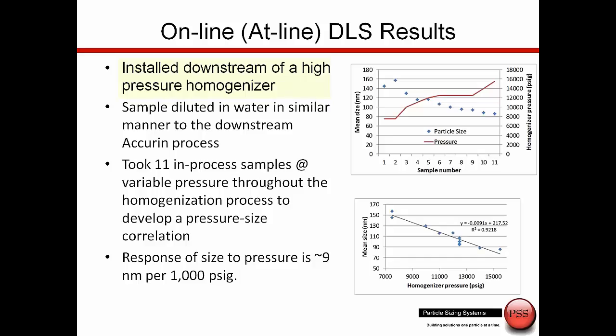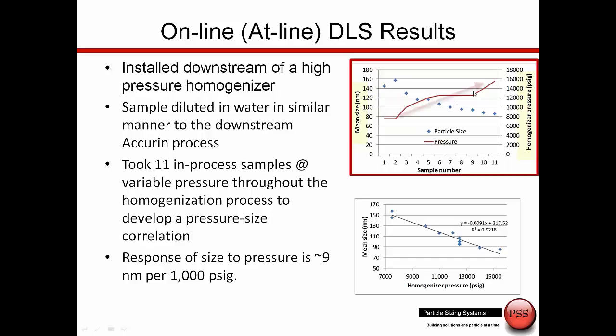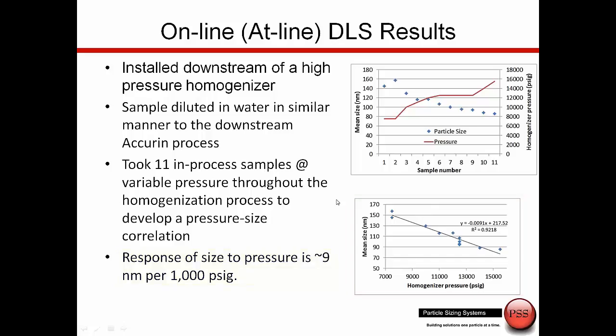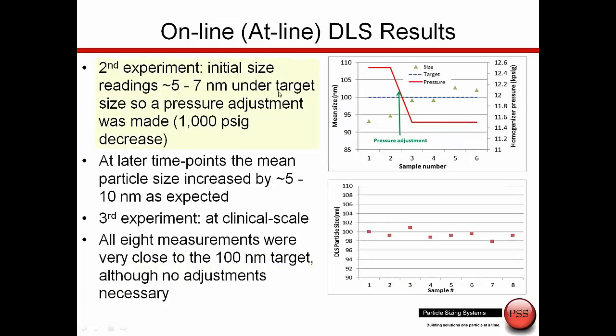The customer wanted to understand what the optimum conditions are for creating the desired particle size. The plot here shows particle size versus homogenizer pressure — the blue diamonds are particle size, the red line is pressure. As we increase the pressure, we reduce the particle size. By creating a series of trials, the customer could understand this response: effectively, every time you reduce the homogenizer pressure by 1,000 PSI, you get a change of 9 nanometers in particle size.